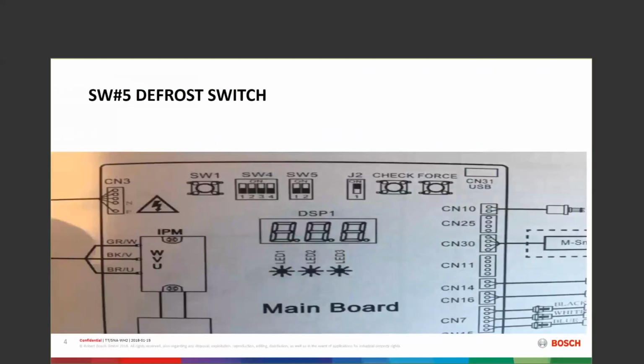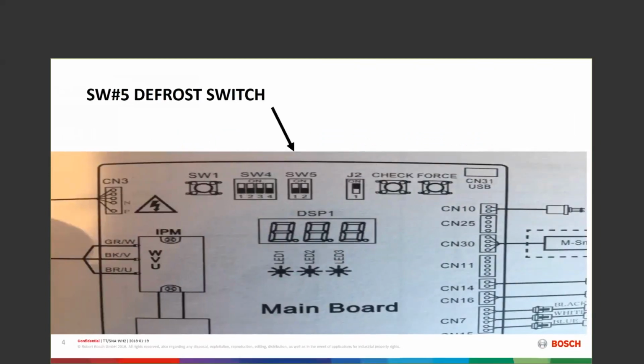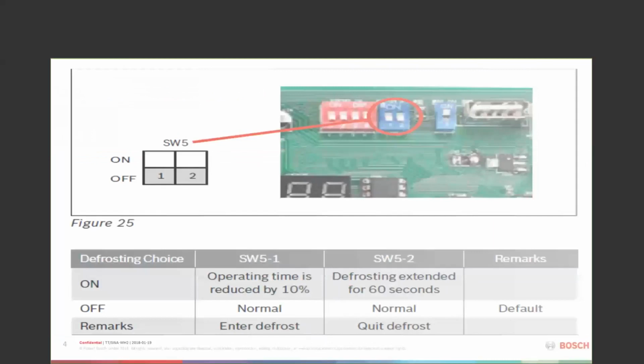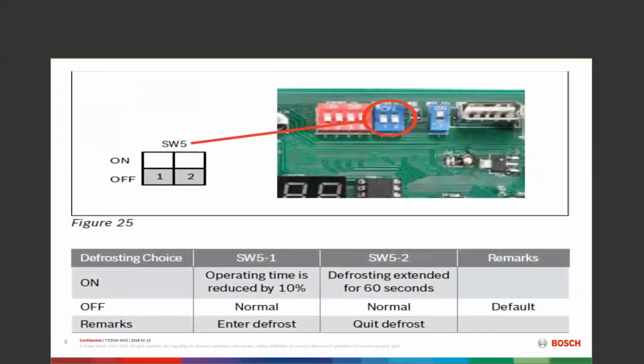SW5 has 2 switches to it. Again, if we're in a normal situation, we're going to leave these switches in the off position. If we're getting into a situation where we're putting this in a heat pump mode and we're down by a lake or we've got a lot of humidity, we might want to reduce that operation time of the normal run time. We might want to take 10% off of that. That's SW51. If we wanted to leave it on while it's in defrost, that is SW52.